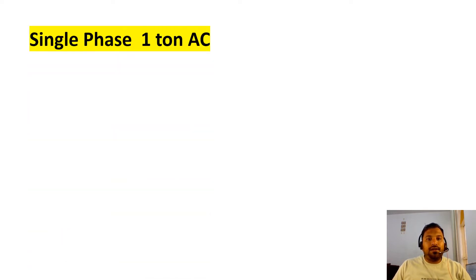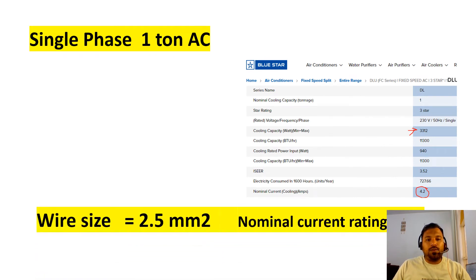Now let us see single phase 1 ton AC rated wire sizes. Single phase 1 ton AC requires 2.5 mm square wire. Basically in this video I consider all are three star rated.